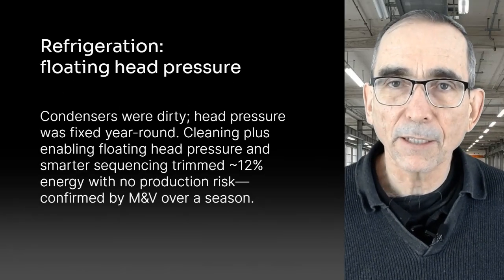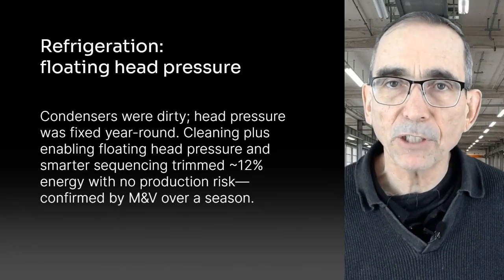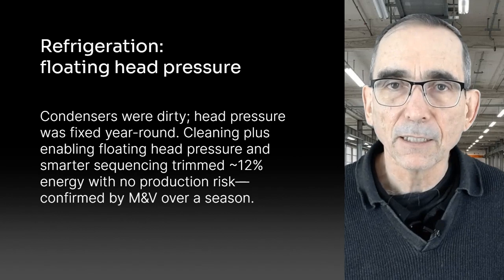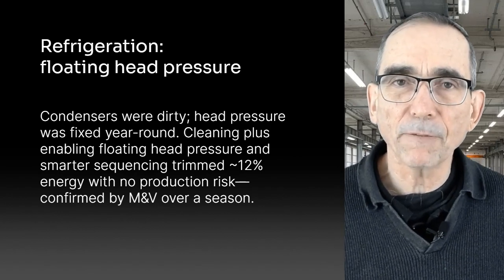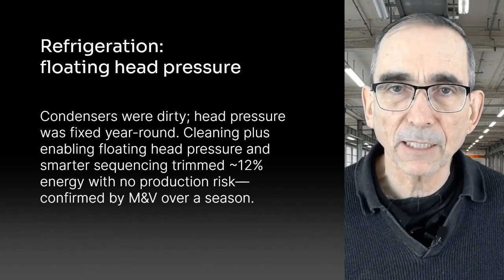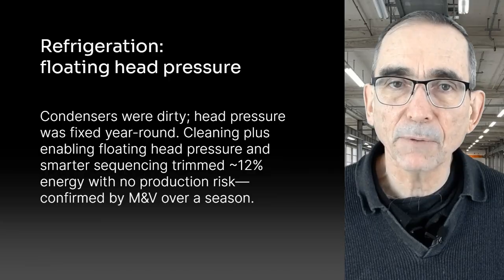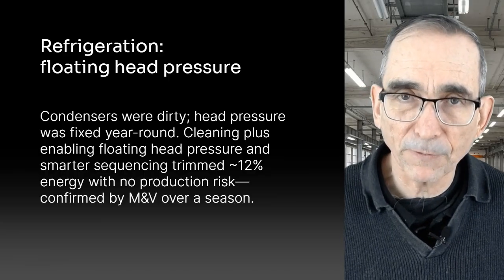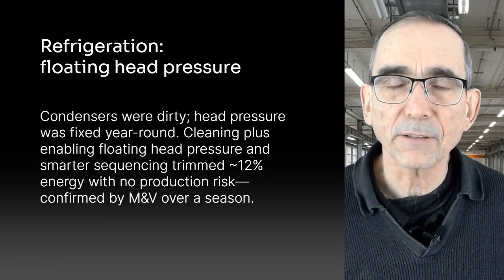Refrigeration: the condensers were dirty and the head pressure was fixed all year round. So cleaning, plus enabling floating head pressure and smarter sequencing, got a 12% energy saving with no production risk, and it was confirmed by M&V undertaken over a season.